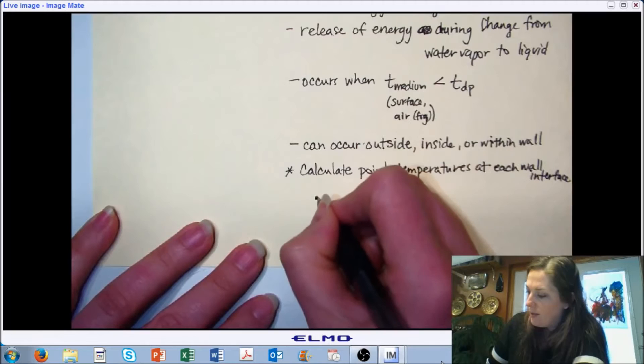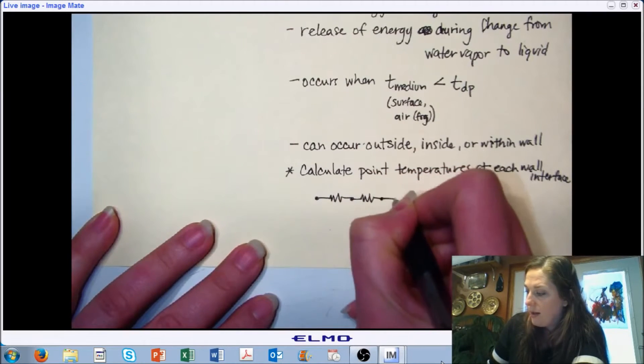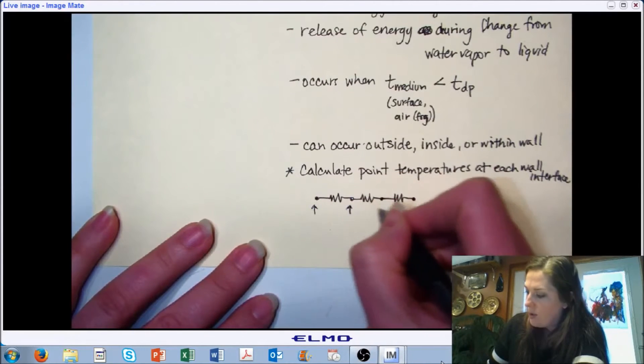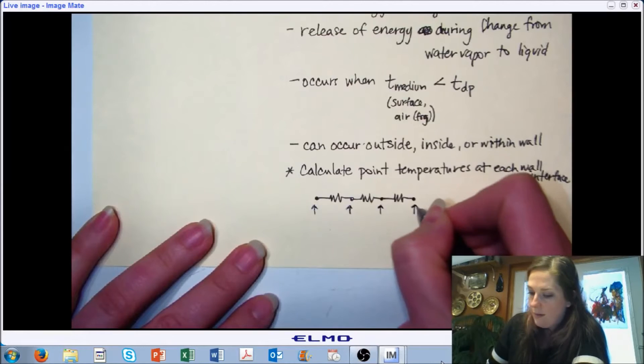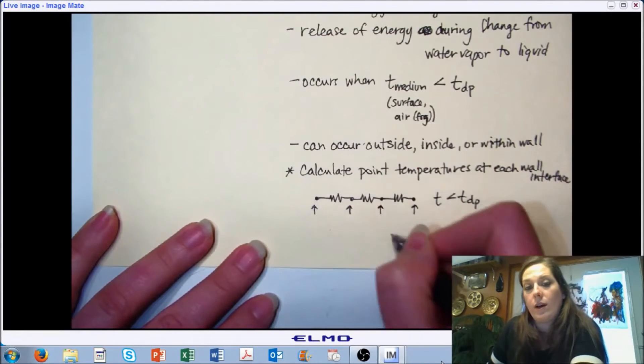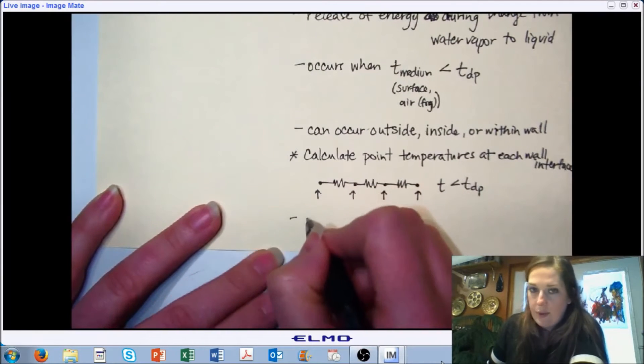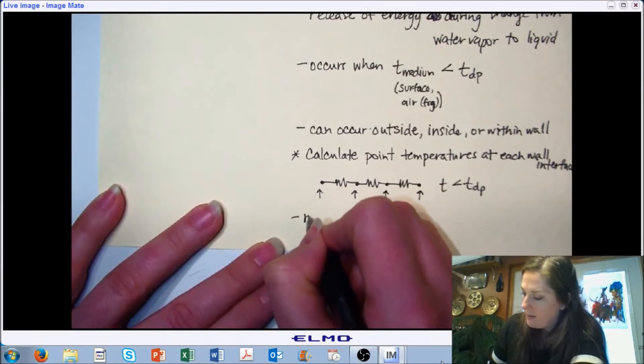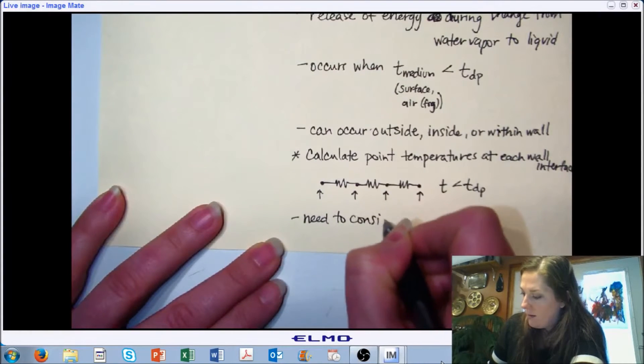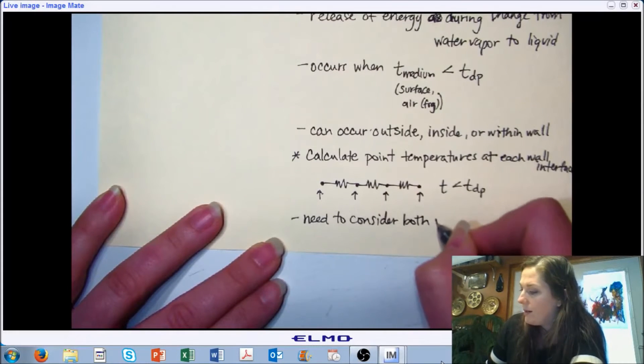And so it looks something like this on our electric analog or our thermal resistance circuit. So essentially you would calculate the temperature at each of your nodes. And if any of those temperatures is less than your dew point temperature, then you have condensation within your wall. It's important to consider this for both winter and summer conditions.